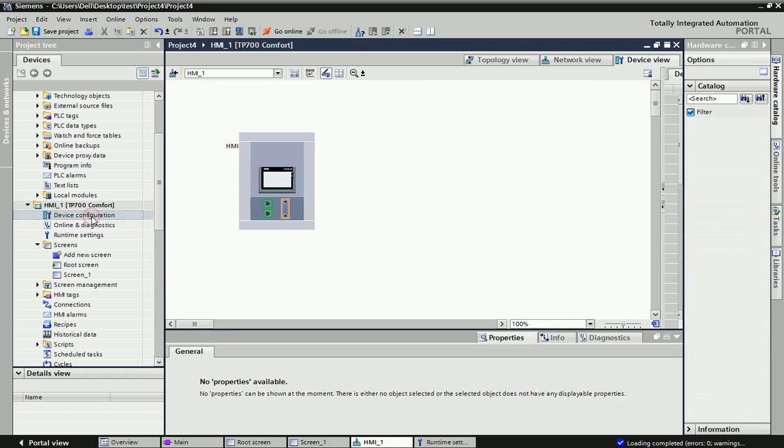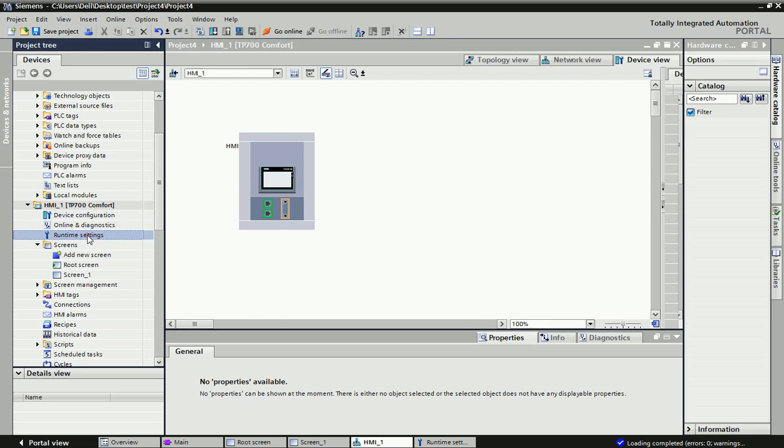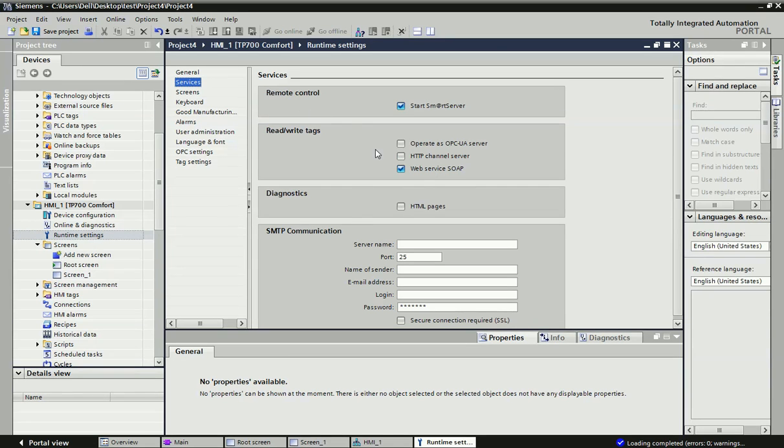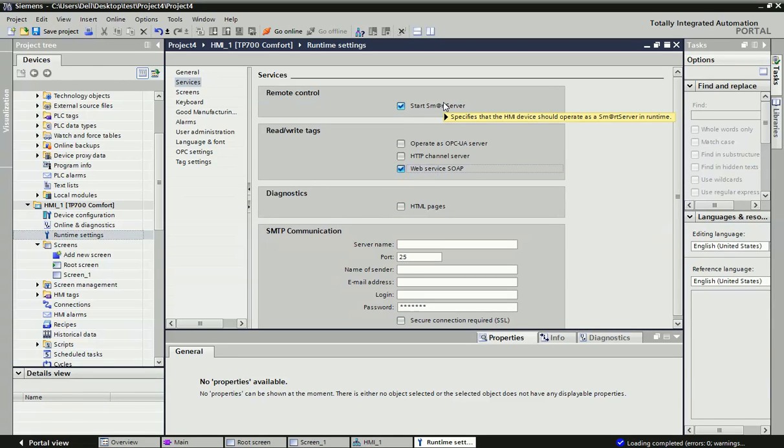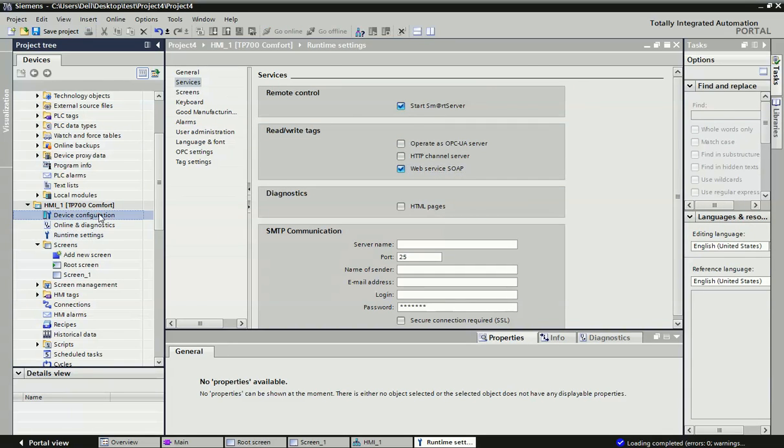First, you need to go for device configuration and set IP address for HMI and PLC. Now we will go for runtime settings, and from runtime settings we need to activate remote control as well as web server. You can see here we need to check this checkbox.